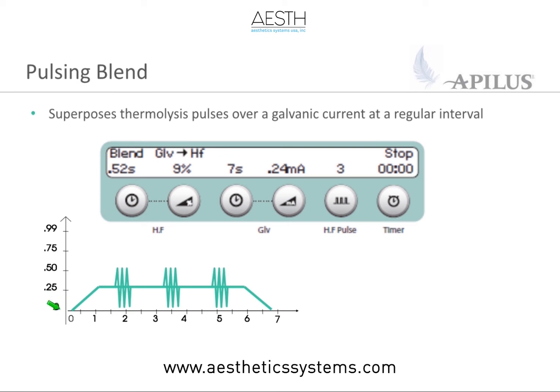Essentially, when we are doing the blend method, we are concerned mainly with the time and the intensity of the milliamps. Milliamps is the intensity for a galvanic current. If we look at this chart here, the galvanic is represented by this line that ramps up slowly, stays consistent for most of the pulse, and then ramps down from there. These are the settings here, 7 seconds, 0.24 mA. Of course, this is hypothetical.